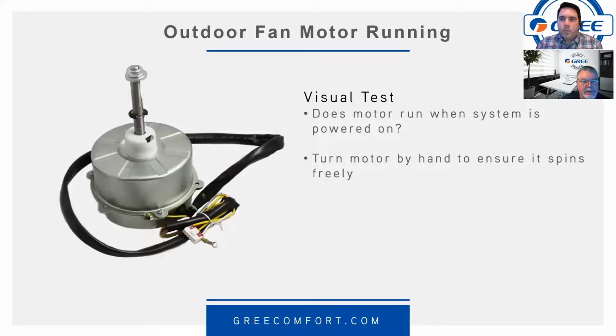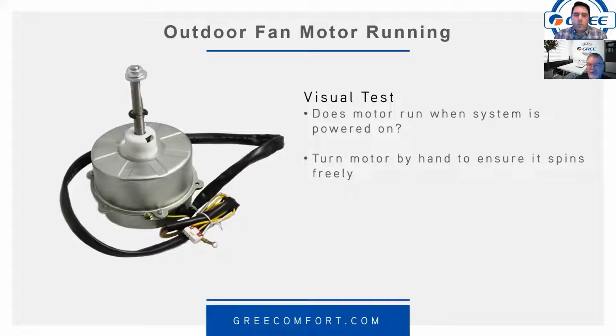Visual test, outdoor fan motor. So outdoor fan motor also stopping running can cause you an E1 in cooling mode. Visual test is fairly easy, but also if you can spin the motor a little bit, because, you know, maybe it's running, but it's bound up a little bit. You know, spinning the fan blade by hand can also be a physical test that can let you know if the thing is operational or should be operational. Could the outdoor unit fan motor stopping cause an E1? Yes. Right? Yes. Cooling mode.